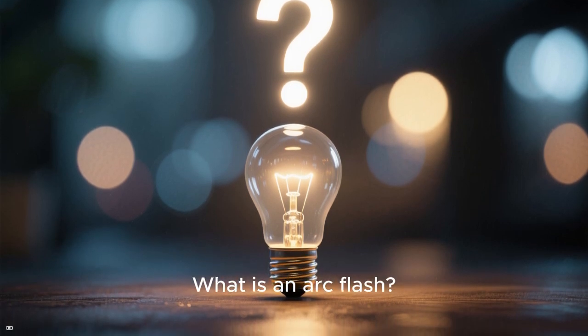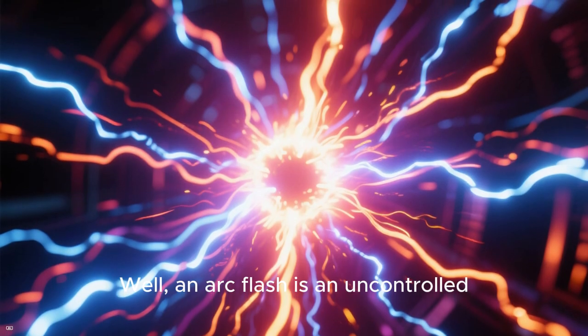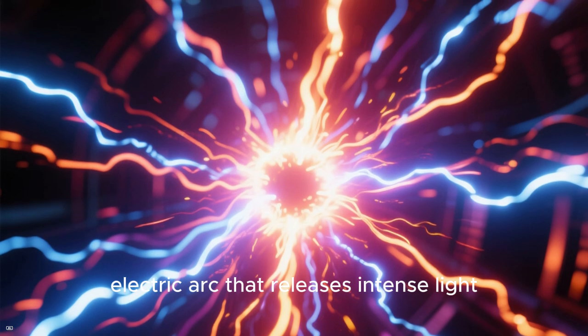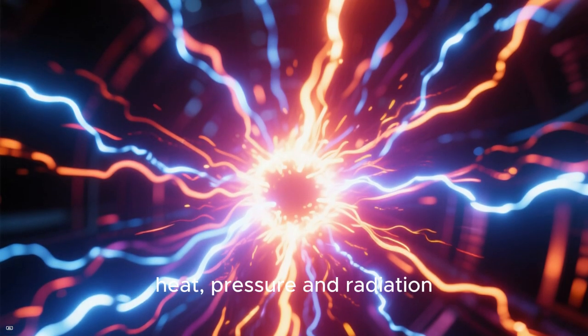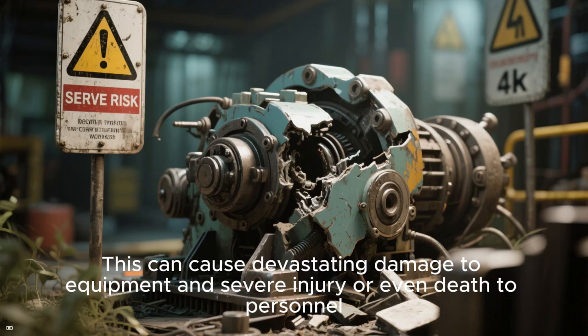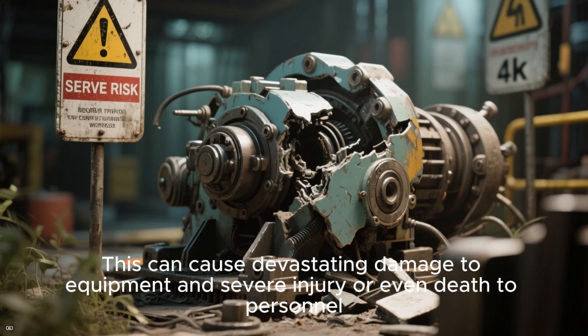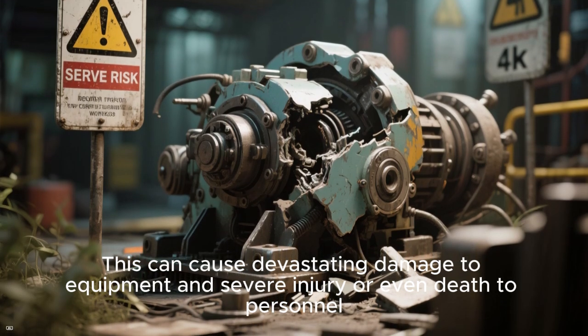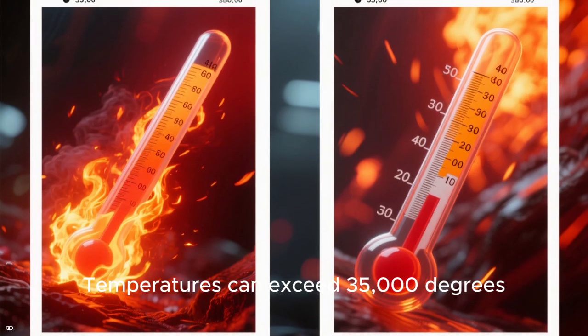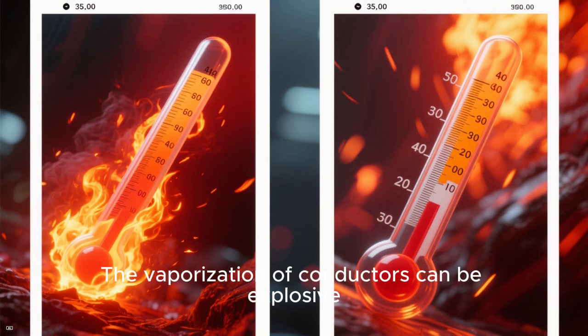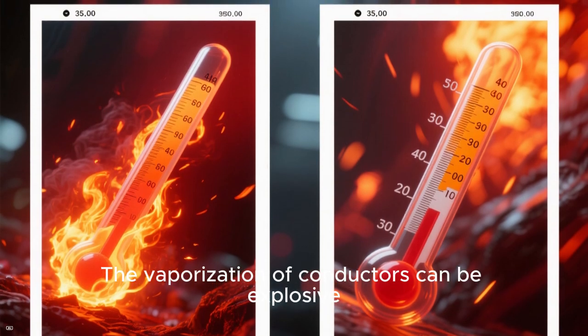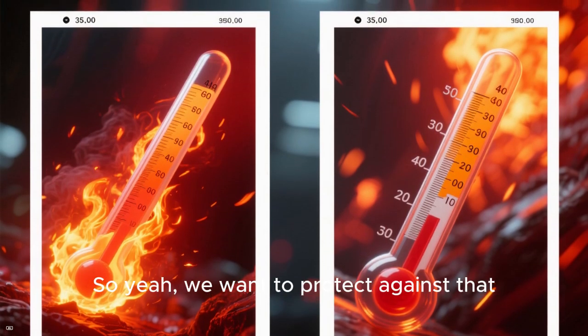What is an arc flash? Well, an arc flash is an uncontrolled electric arc that releases intense light, heat, pressure, and radiation. This can cause devastating damage to equipment and severe injury or even death to personnel. Temperatures can exceed 35,000 degrees Fahrenheit. The vaporization of conductors can be explosive. So yeah, we want to protect against that.